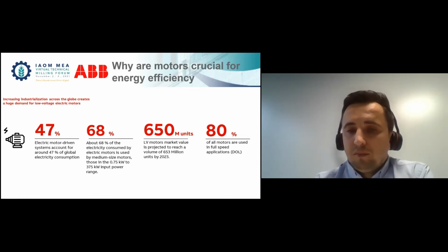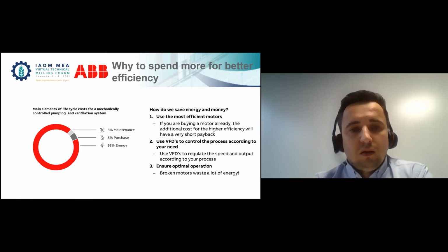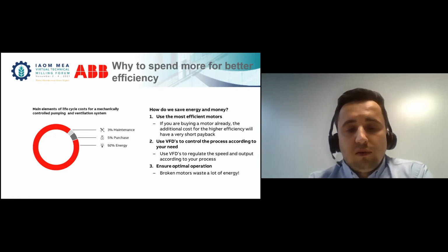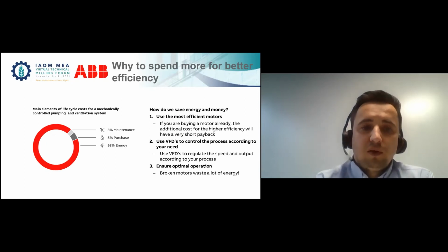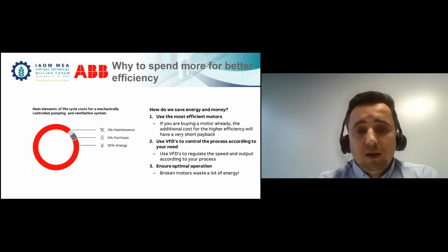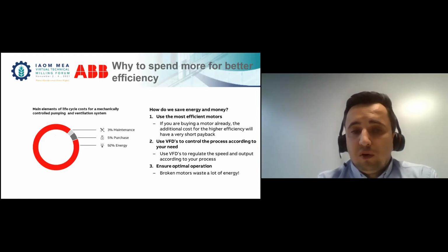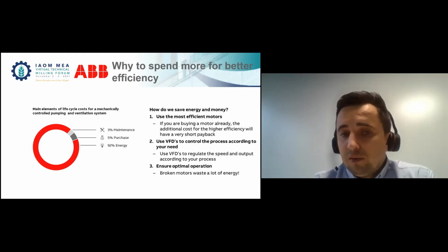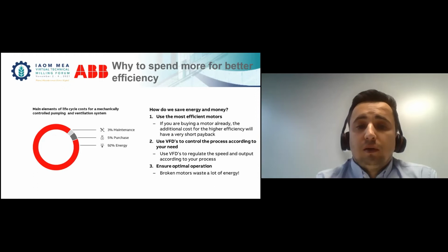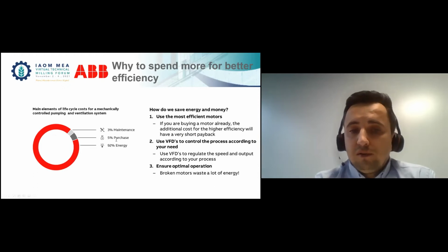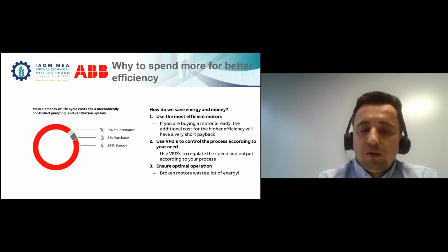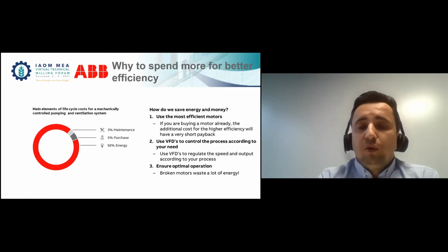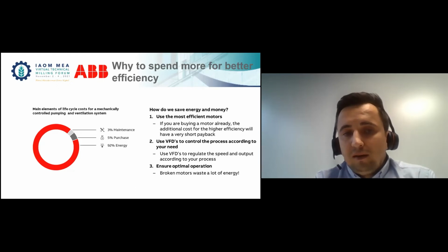And what is the total lifetime cost of a motor, as we can see here, for a motor which is running 20 years as an example? The purchasing cost, or the initial cost to buy the motor, is only 5% compared to the very huge amount of 92% energy consumption during its lifetime.